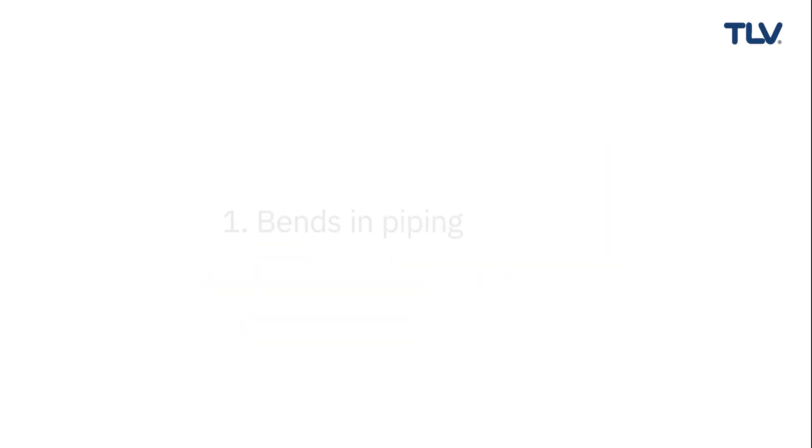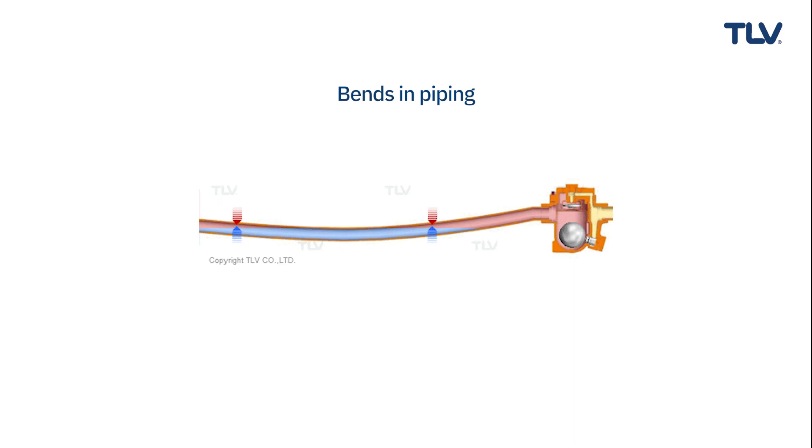There are two other issues to account for when installing trap inlet piping. One is bends in piping, and two is narrow piping. Bends in piping occur when the required piping supports are not installed. This creates curves in the piping where condensate accumulates and steam can become trapped.